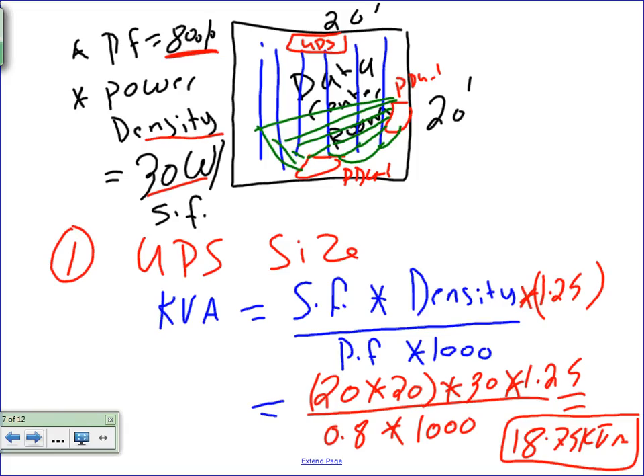But we don't know what the servers are, so that's kind of an acceptable rule. Right now, if you talk to a guy here, guys will tell you this number is 200 watt per square foot now. So if it's 200, would anything change other than the calculation? The method stays the same. You just put 200 instead of 30. Okay? Any question about 18.75 kVA?